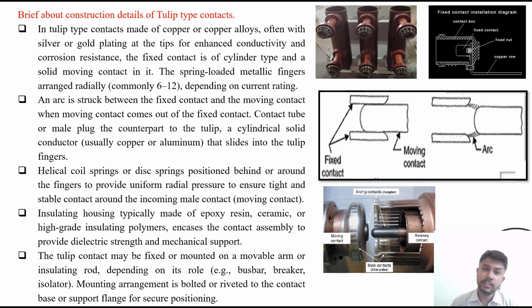Brief about construction details of tulip type contacts in circuit breaker. So in tulip type contacts, it is made up of copper or copper alloys, often with silver or gold plating at the tip for enhanced conductivity and corrosion resistance. The fixed contact is of a cylinder type and the solid moving contact goes in it.